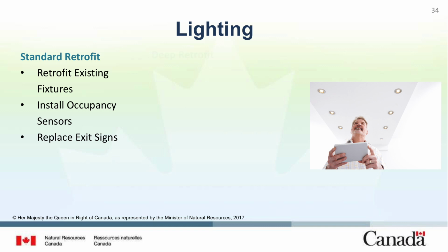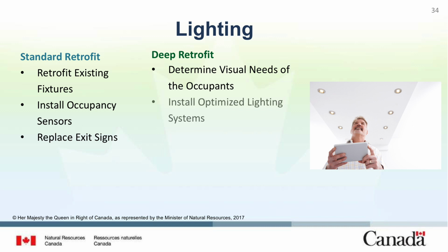As you move into a deep retrofit, you'll be taking a fundamentally different approach to lighting. The first step is to make sure that you're determining the visual needs of the occupants. You need to make sure that you're hitting the appropriate illuminance levels within the space. After you've done that, you need to determine an optimal lighting solution for that space. For example, you should move towards using a lighting power density metric to determine the appropriate fixture type to meet a specific watt per square meter threshold that you want to hit.